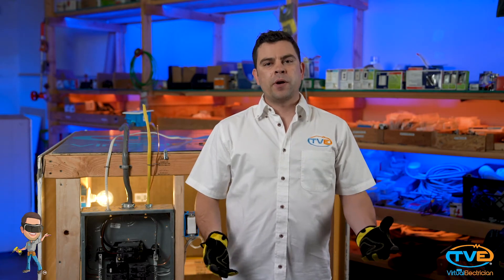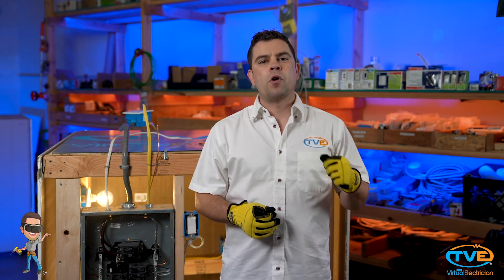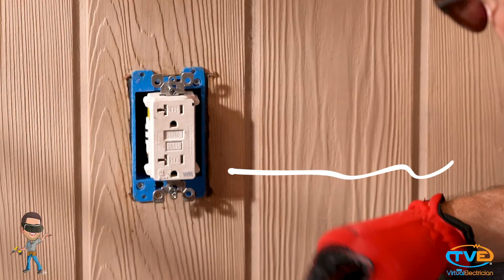If you choose to direct bury wire, you must use UF cable. This is specifically designed for direct burial. Outside outlets and GFCIs should have a WR stamped on them — this stands for weather-resistant.